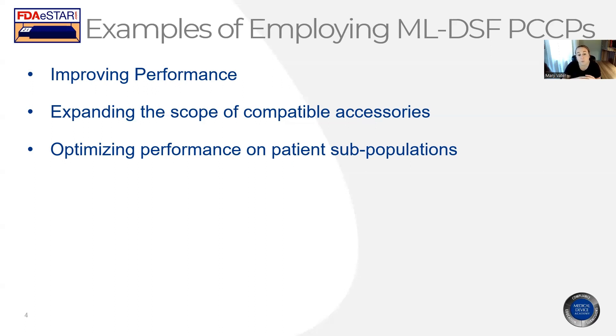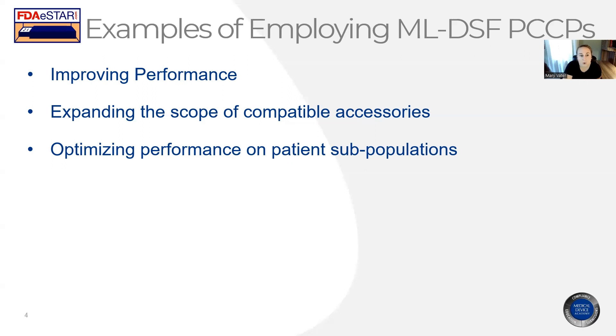The last example is if you intend to optimize performance on a patient subpopulation. That could be if you have a specific group where you want to improve specific performance, but you might not have the comprehensive data set yet. Once you have that data, you can expand your claims to those specific subpopulations, and you could clear that through the FDA in a PCCP as well. Those are just a few examples — the guidance document lists a couple more — but basically those are all changes that would normally require a new submission, but you would be able to get pre-authorization for through a PCCP.